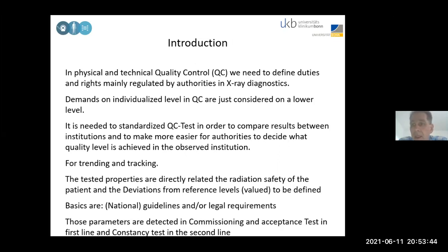And the second one is that if you are visited by authorities, as some countries have these mandatory visits, then they can check what you have done. If you have deviations from the program which you should assess, then you can discuss, or you can find out where the problem is, or whether your machine has a problem. I would call it trending of the machine. Sometimes you see that a machine starts aging and the output of an X-ray tube is going down, and you can actually see that with your quality control. That puts you in the position that you either tell the vendor that something needs to be done to improve the output from the X-ray tube, or in the worst case, you have to exchange the X-ray tube.